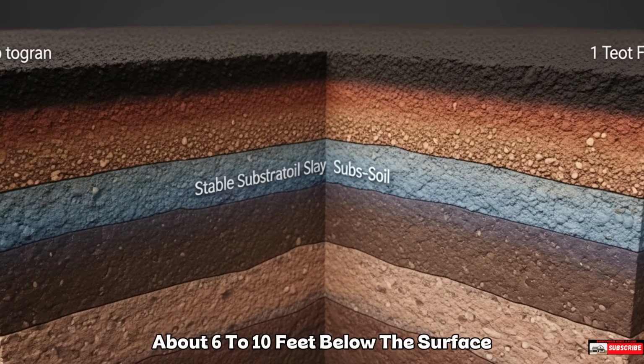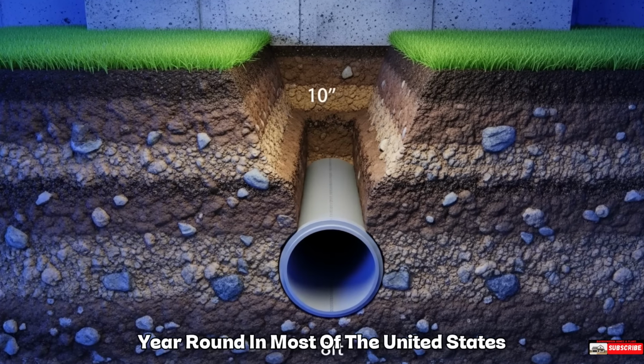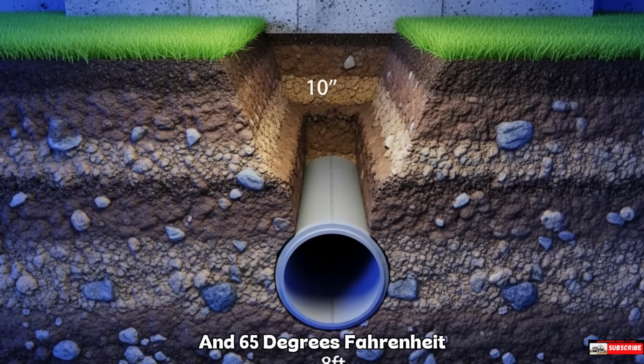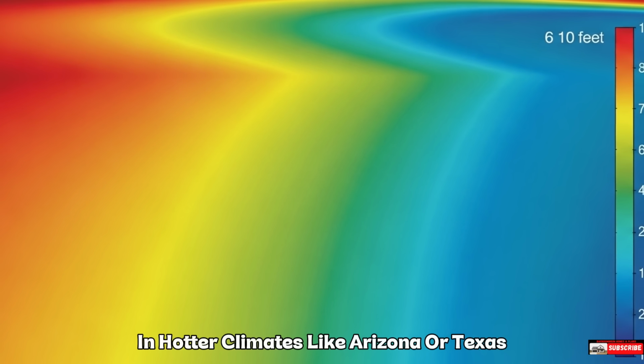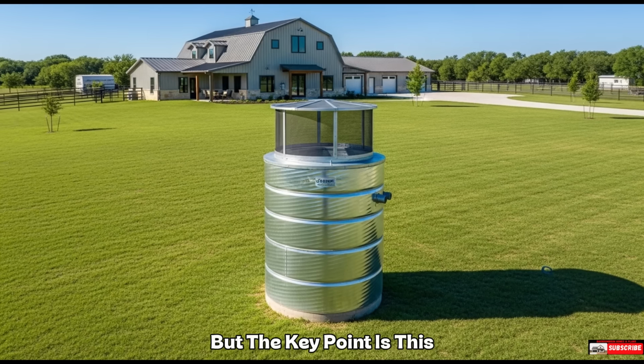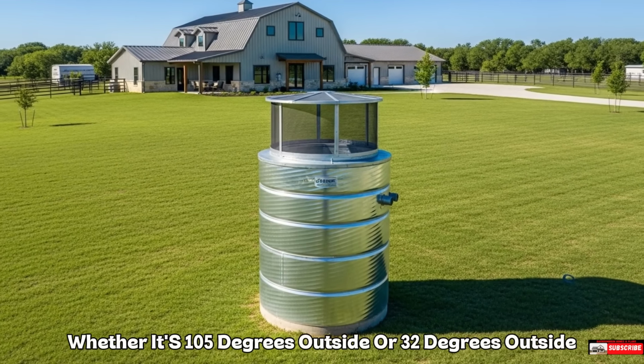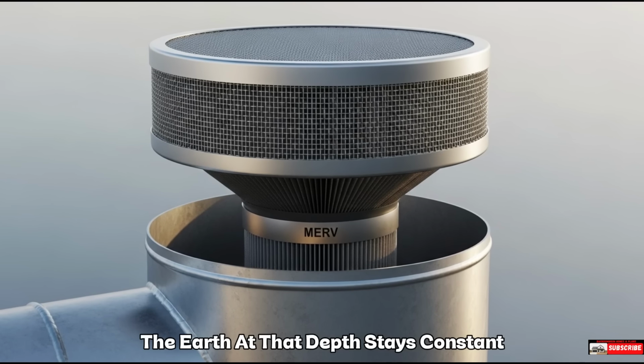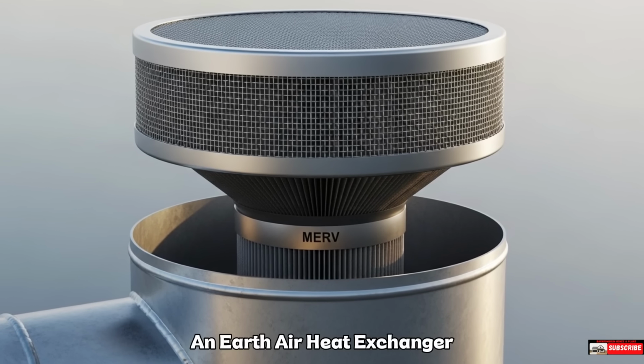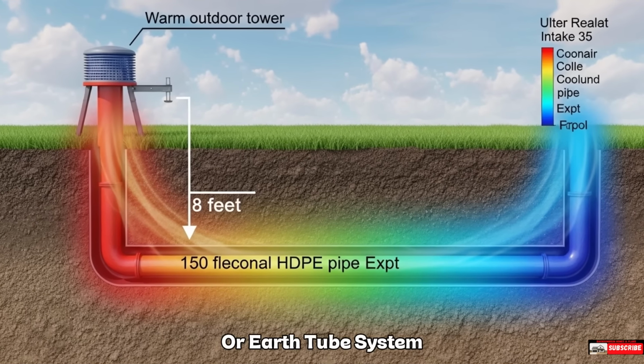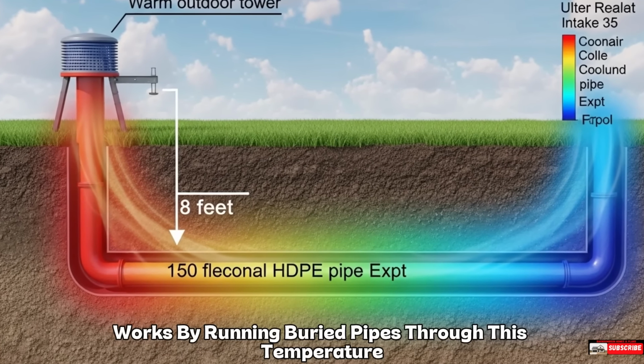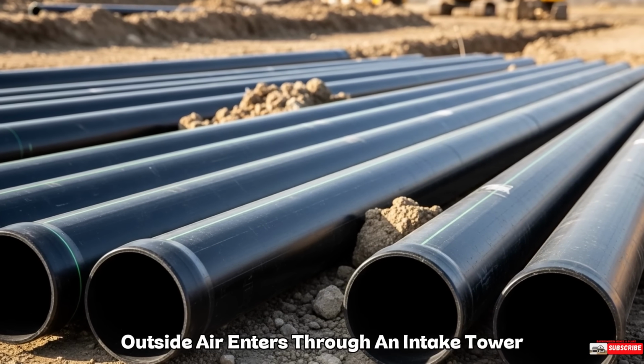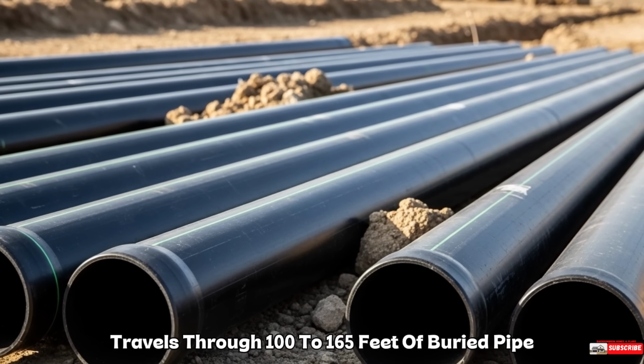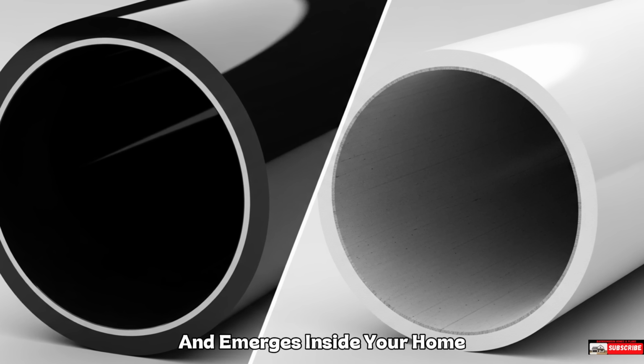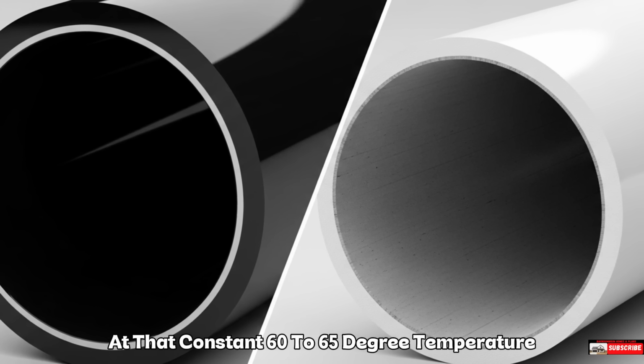Engineering the earth-air heat exchanger. Here's how this works. About 6 to 10 feet below the surface, the Earth maintains a nearly constant temperature year-round. In most of the United States, that temperature is between 60 and 65 degrees Fahrenheit. In hotter climates like Arizona or Texas, it might be 65 to 68 degrees. But the key point is this: it doesn't fluctuate. Whether it's 105 degrees outside or 32 degrees outside, the Earth at that depth stays constant. An earth-air heat exchanger, also called an EAHE or earth tube system, works by running buried pipes through this temperature-stable zone. Outside air enters through an intake tower, travels through 100 to 165 feet of buried pipe, exchanges heat with the surrounding earth, and emerges inside your home at that constant 60 to 65 degree temperature.